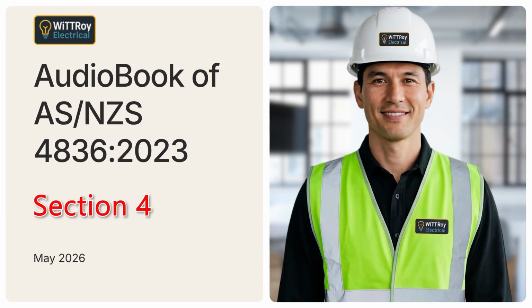In practical terms, do not judge the danger only by looking at the incoming supply. The equipment itself may step up the voltage or produce dangerous voltage under certain conditions. Current transformers need special care. An open-circuited current transformer secondary can produce high voltage and place a worker in serious danger. Clause 4.3.9.